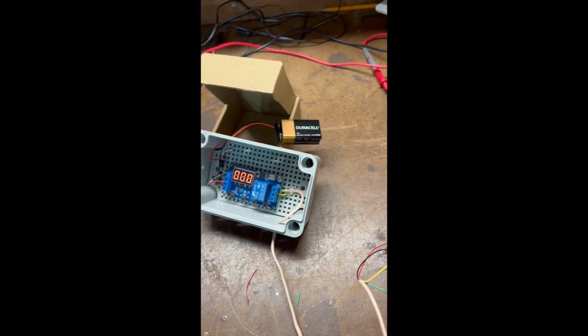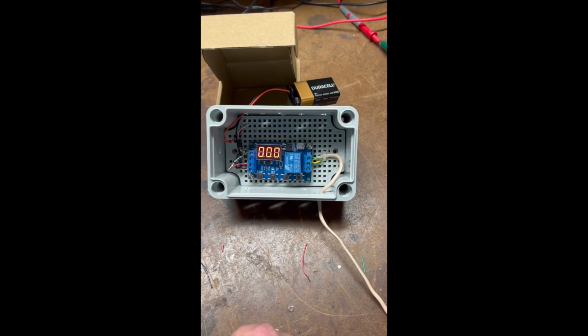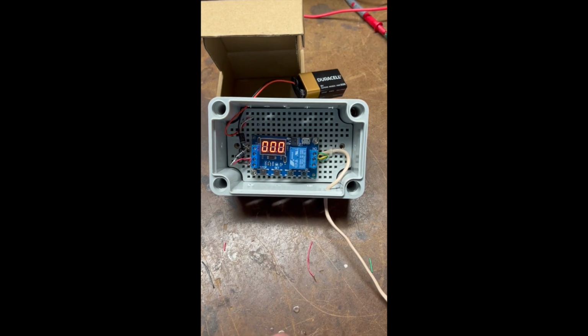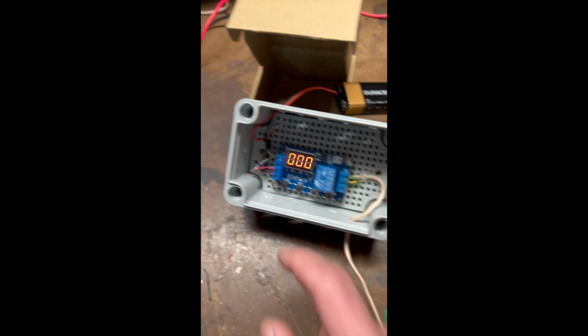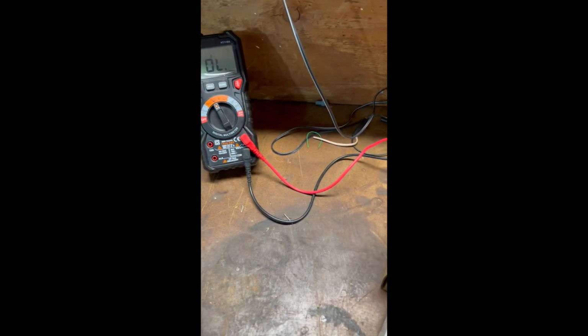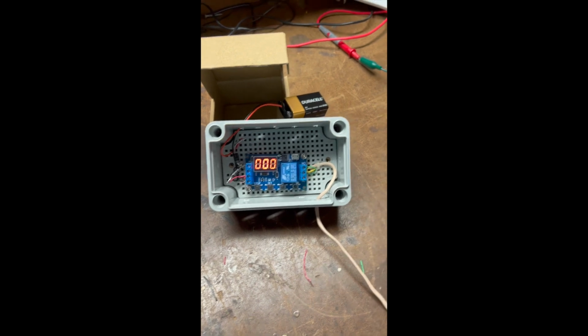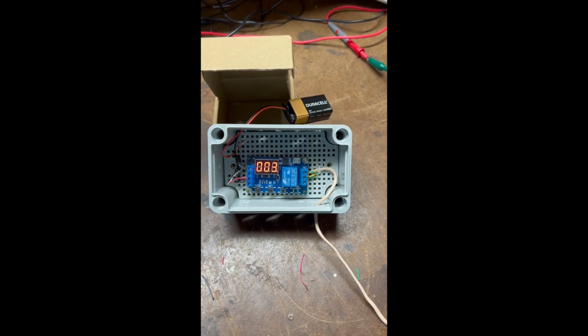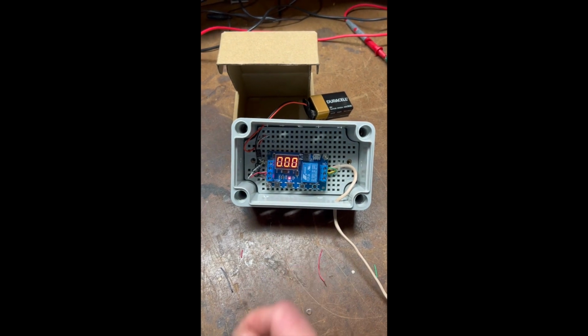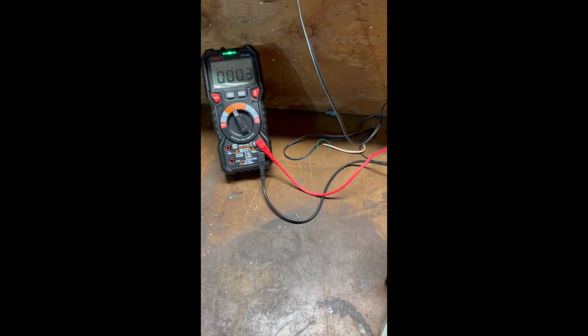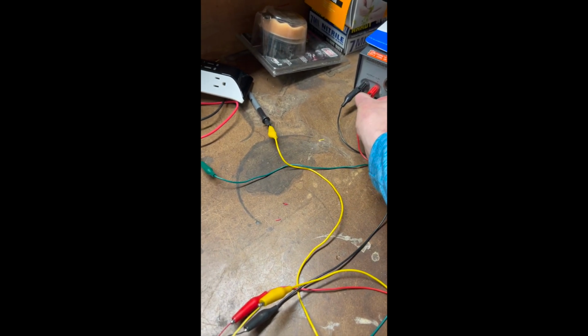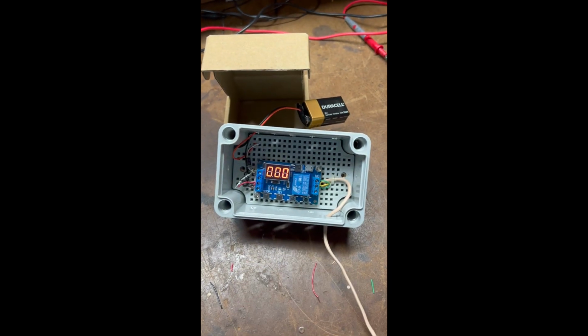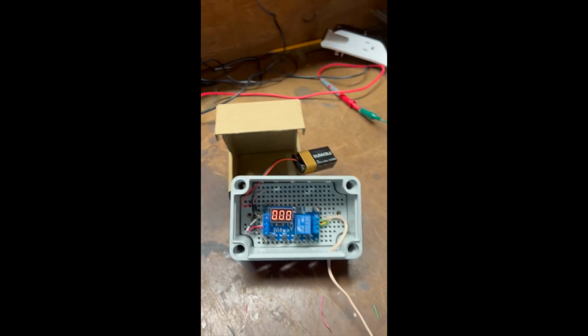So now you see that this red light is not on. That means the relay is not energized. I'm in a normally open condition and my ohm meter is reading open. So life is good. I have no alarm condition. If I remove power from the device, you'll see my countdown timer starts. The relay will energize and I have an alarm position at this point. We connect power again. The relay de-energizes and I have an open position.